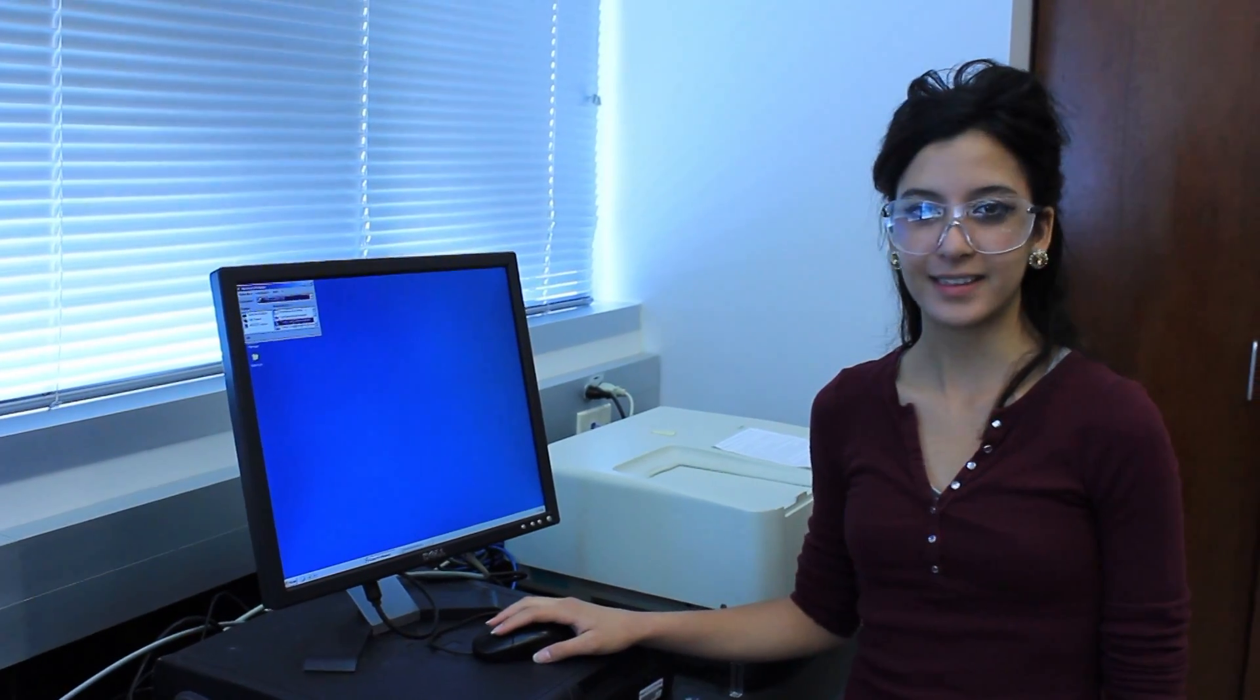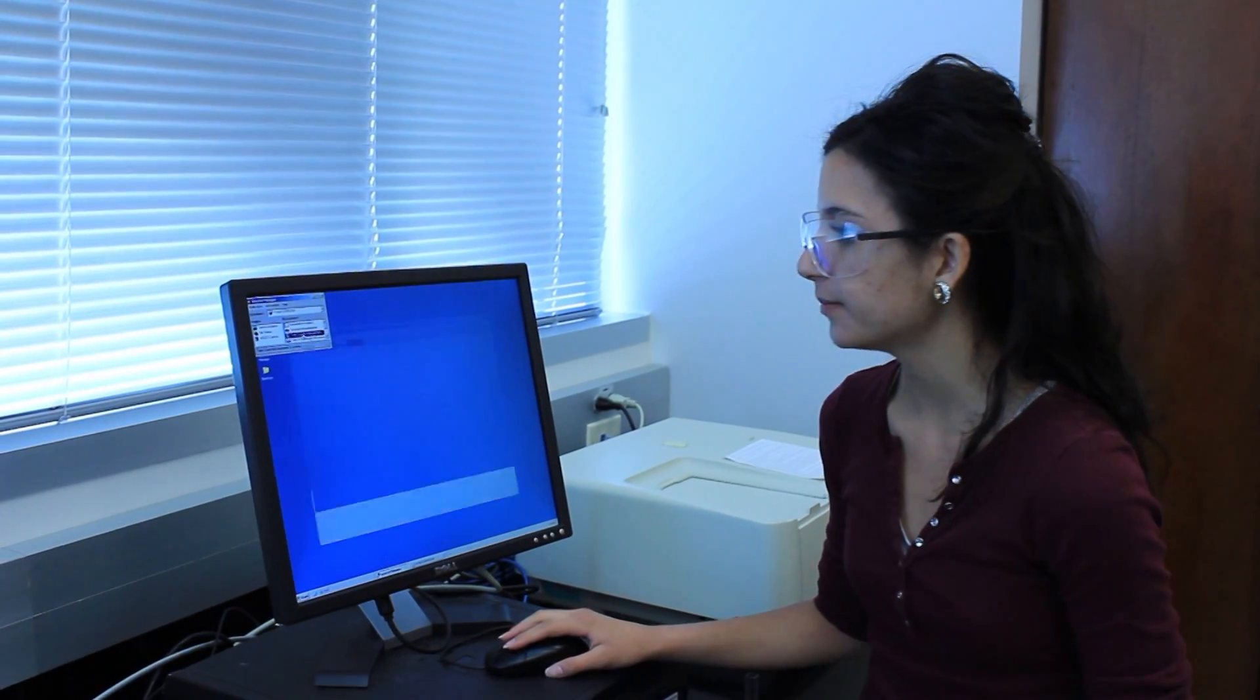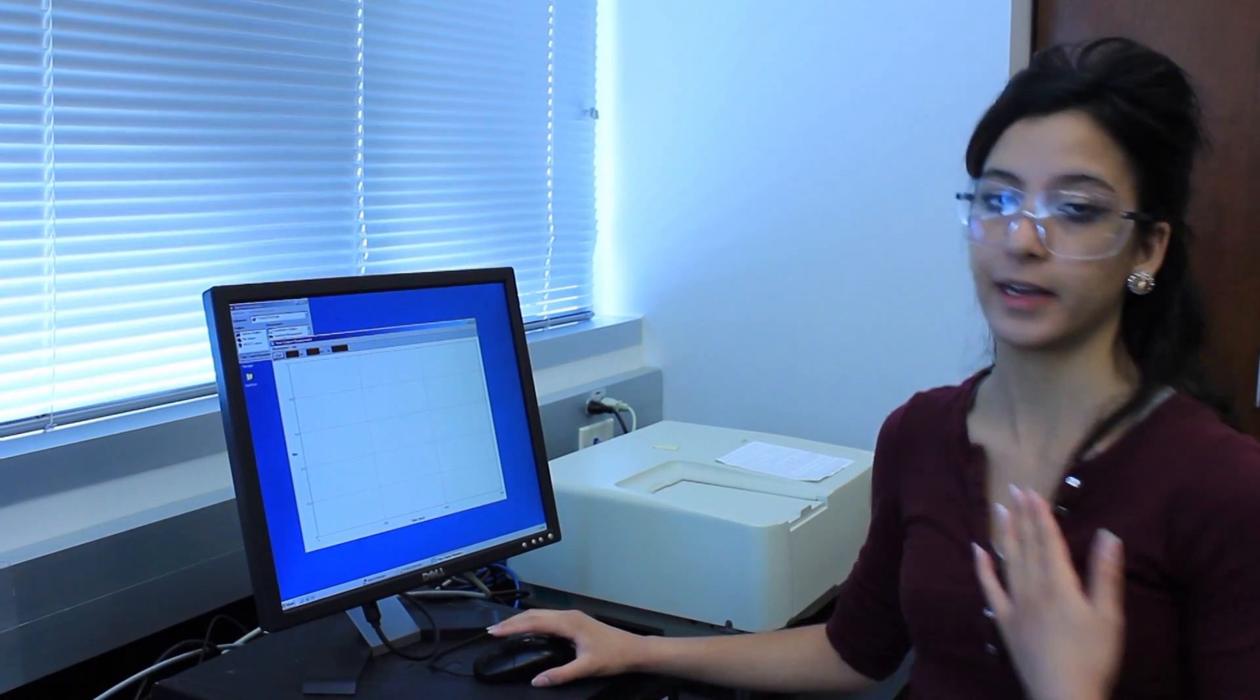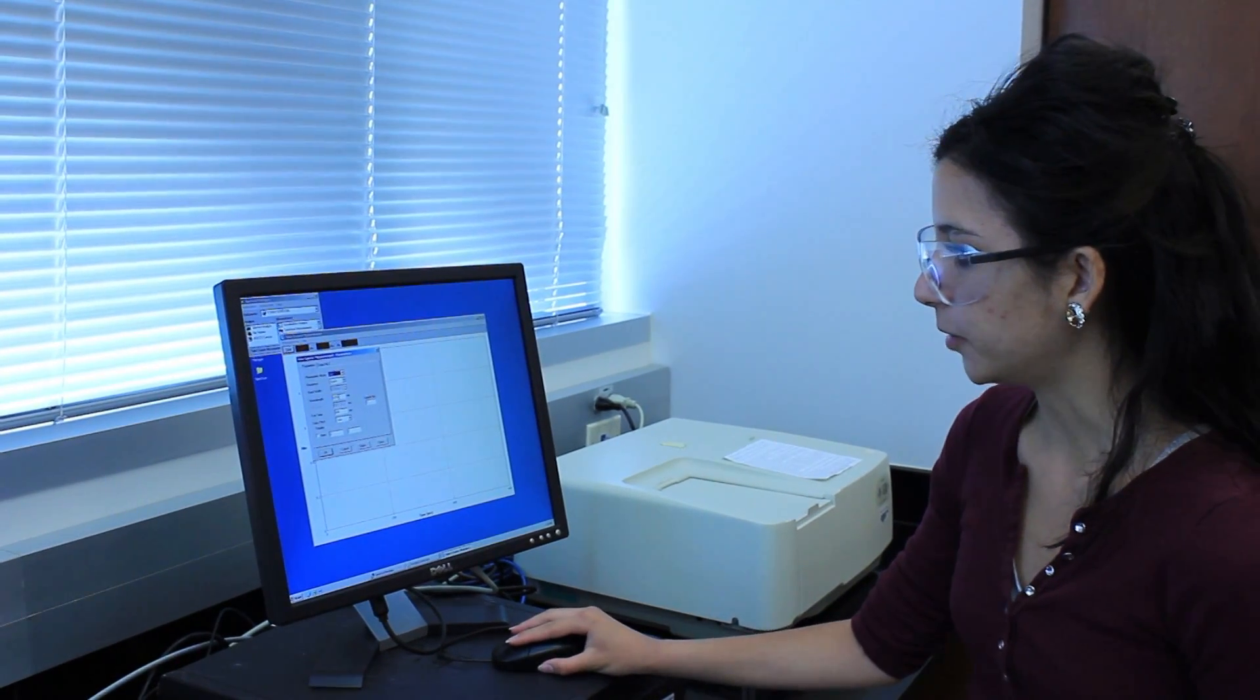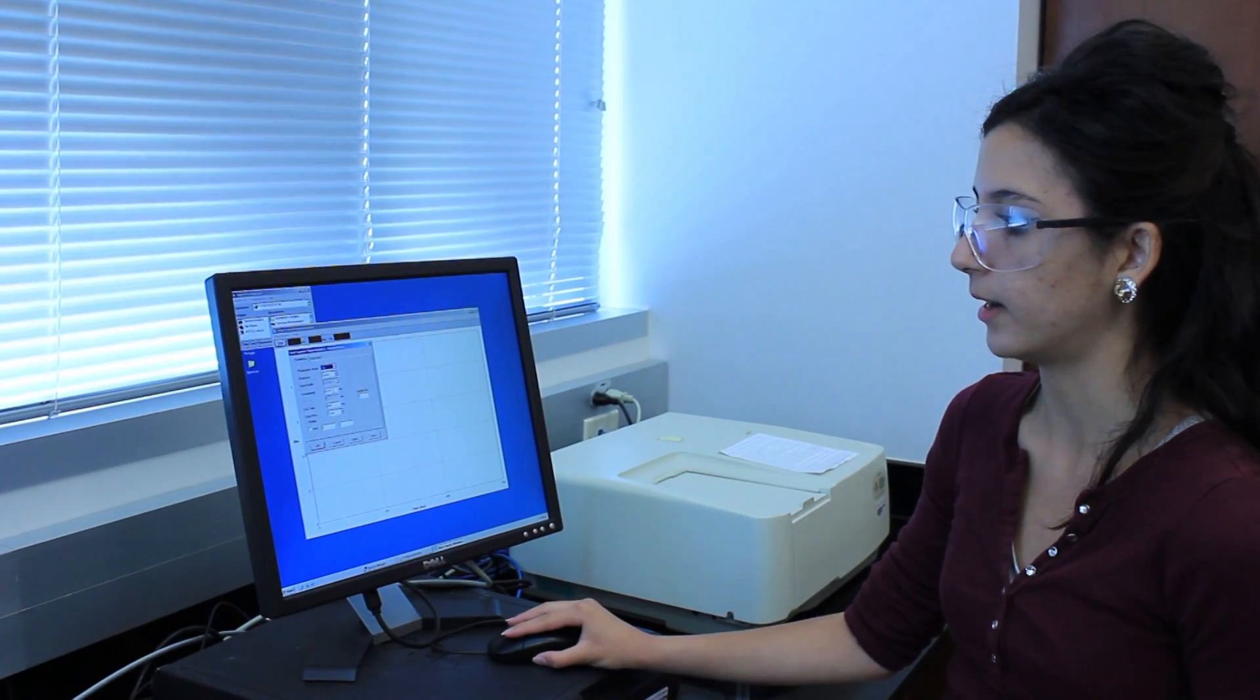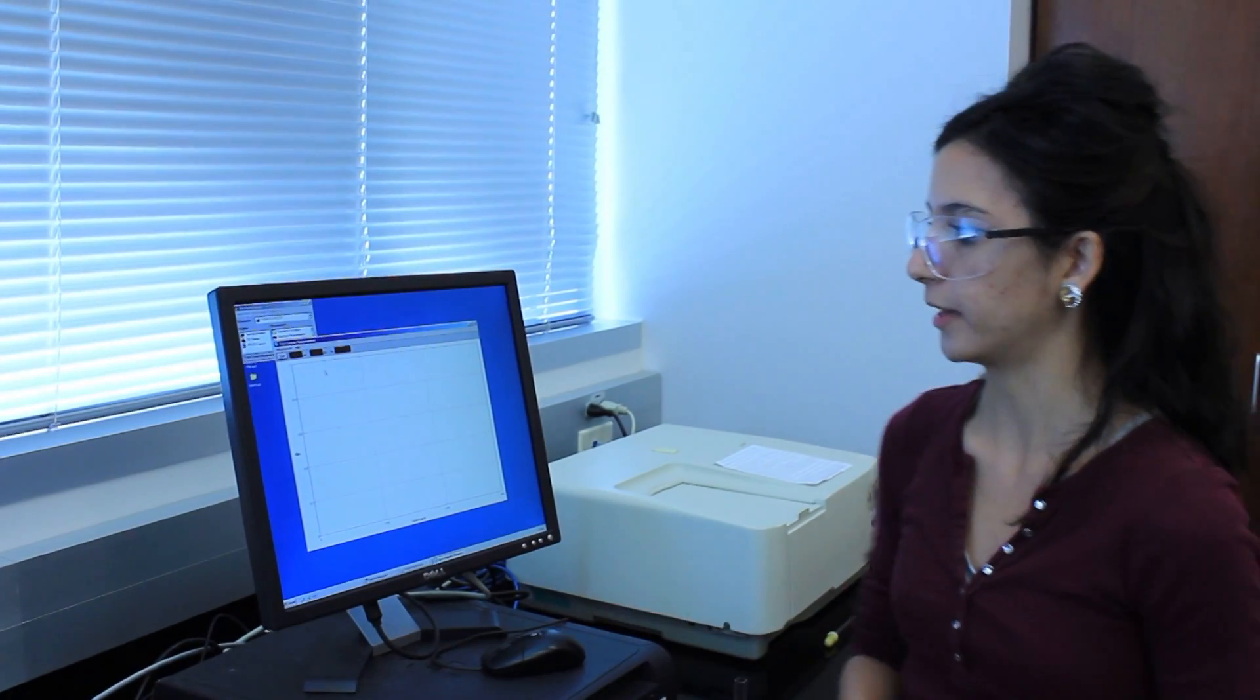For the kinetic data collection you'll be using time course measurement. So you click on time course measurement for the machine and then you want to set it to the analytical wavelength you found. In our case that was 629 nanometers. So you go to measurement, parameters and then you enter that right here. The wavelength should be your analytical wavelength, again in our case 629. And you just hit ok and you're ready to measure your next part.